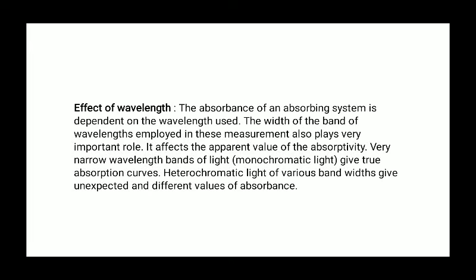The absorption of an absorbing system is dependent on the wavelength used. The width of the band of wavelength employed in this measurement also plays a very important role. It affects the apparent value of the absorptivity. A very narrow wavelength band of light, monochromatic light, gives the true absorption curve. Heterochromatic light of various bandwidths gives unexpected and different values of absorbance.